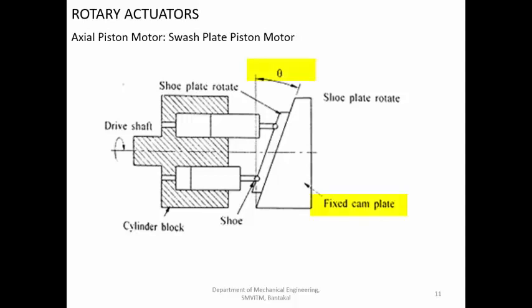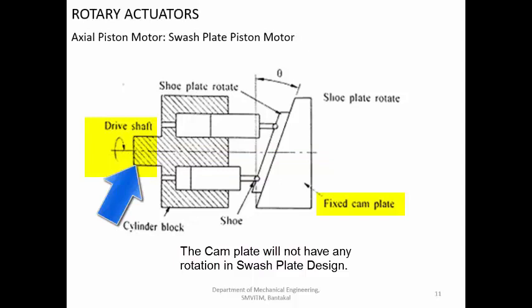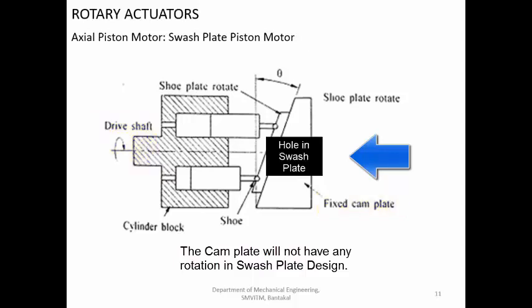Now why is it called axial piston motor? It is called axial piston motor because this is the axis of the output shaft — that is the drive shaft — and the piston axis is parallel to that axis. That is why it is called an axial piston motor. You are having a fixed swash plate, so it is a swash plate piston motor. You can have the drive shaft on one side or on the other side — both designs are possible. If you have the drive shaft on the other side, the swash plate will have a cavity in the middle through which the drive shaft is taken out.